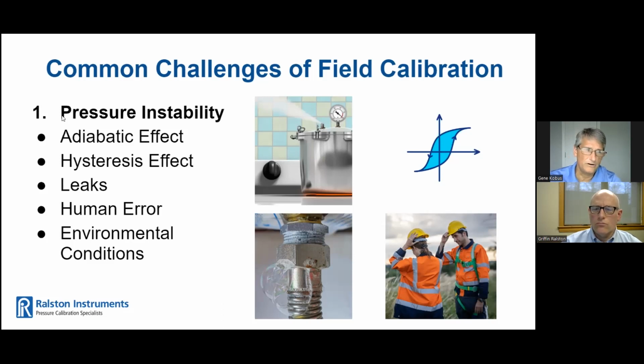Some of you may have heard of the adiabatic effect. This is where you generate a lot of pressure in a short amount of time, such as when using a hydraulic pump, and as you're pumping, you're creating a lot of heat. As the heat builds, pressure goes up. The problem is when it cools, it tricks people into thinking it's leaking because you'll see the pressure dropping. That's probably one of the calls we get a lot about with a hydraulic pump — it's one of its downfalls.